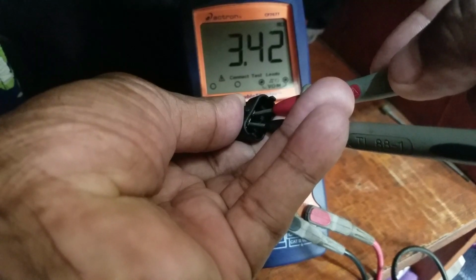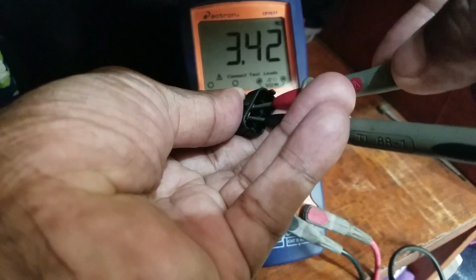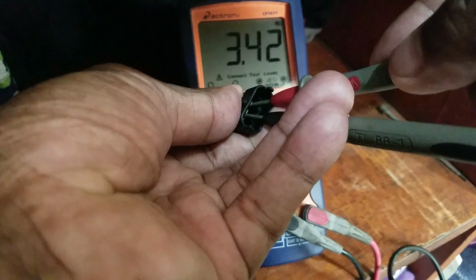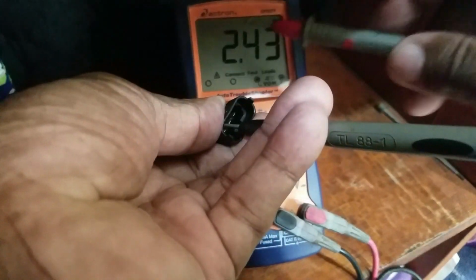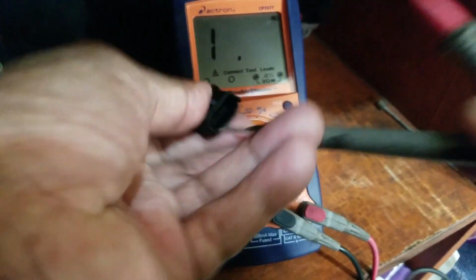We got a 3.42 mega ohm rating. It needs at least a 4.87 mega ohm resistance. So according to that, this sensor is bad.